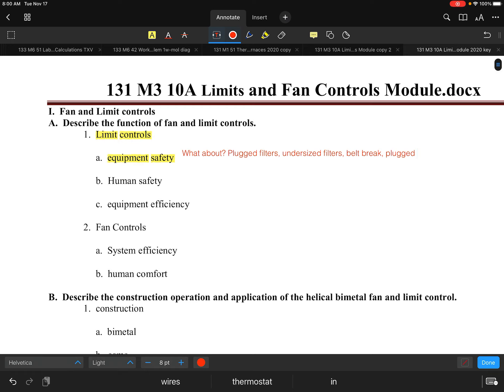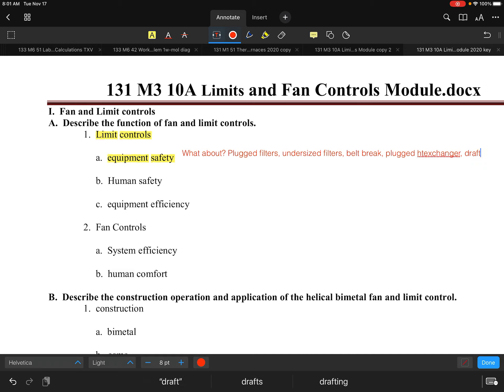Another issue, especially on condensing furnaces, is a plugged heat exchanger. Blockages can be external or internal. Internal restrictions inside the heat exchanger can result from sooting, excessive condensate, or issues with drafting — an inability to properly draft the unit.